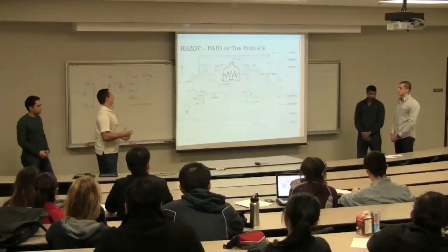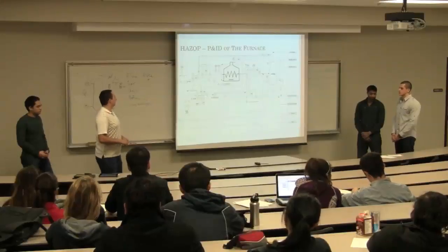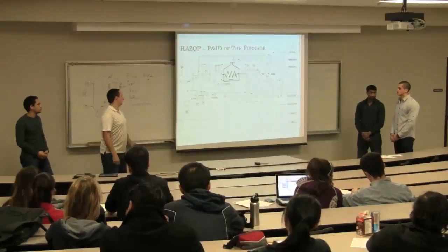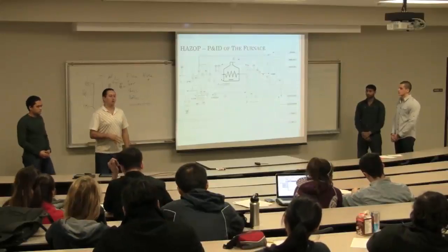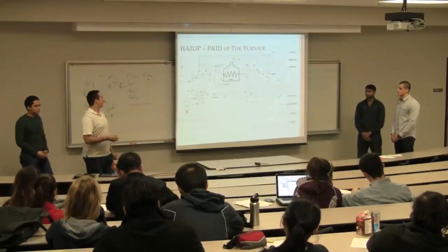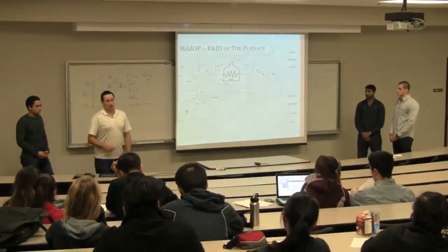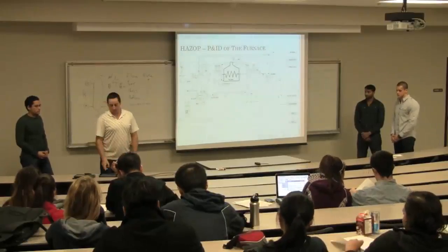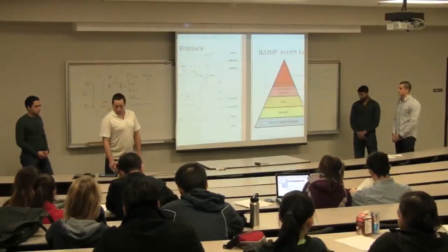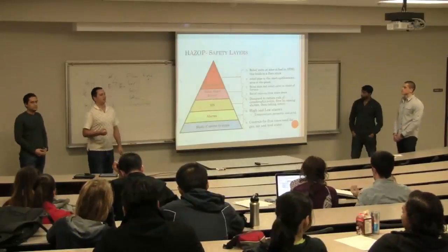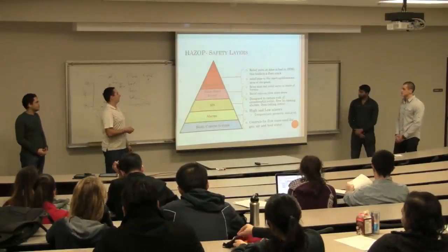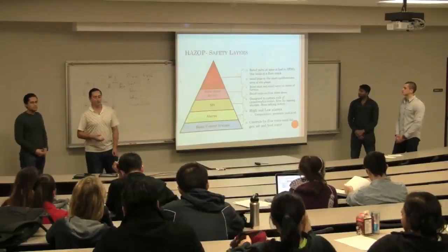Inside of those, the composition was only looked at for the mixing point for the fuel and the air, because at the other point we're just having water come through. But we did look in case some causes could be foulings or pipe leaks as well. So based off of our HAZOP of those two nodes and those parameters, we determined the levels of safety that have to be installed.